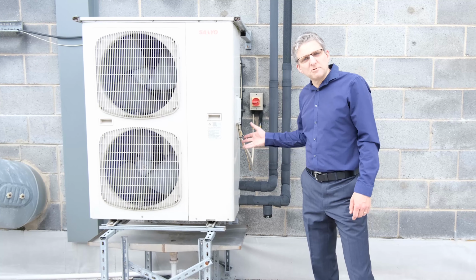It's quite common also to have a split system where you have the outdoor evaporator and fans in the box outside, and you have the other components in another enclosure inside the building. And the two parts in the split system are connected together, not with water pipes, but with refrigerant pipes. So they have to be installed by a refrigeration engineer, rather than this system which can be installed by a heating engineer and an electrician.